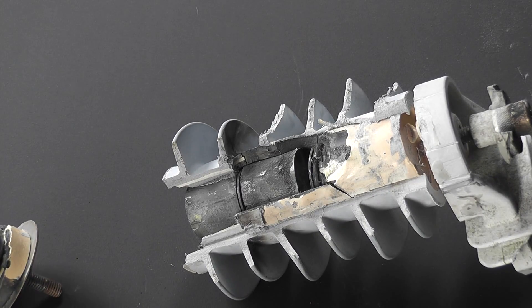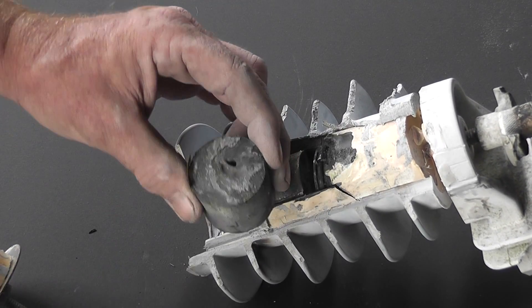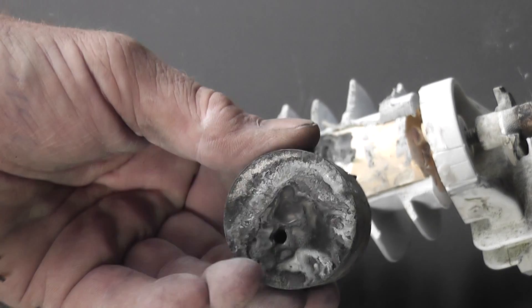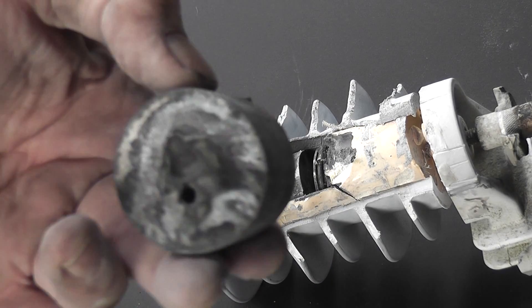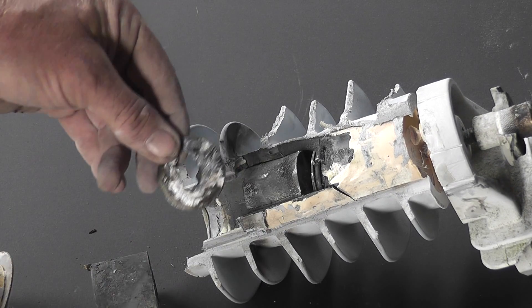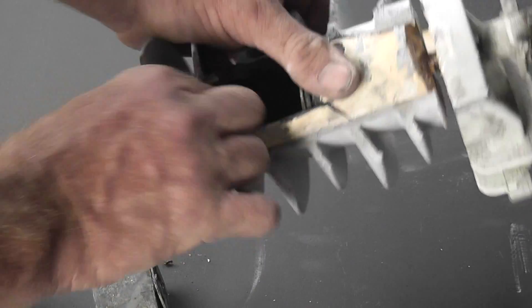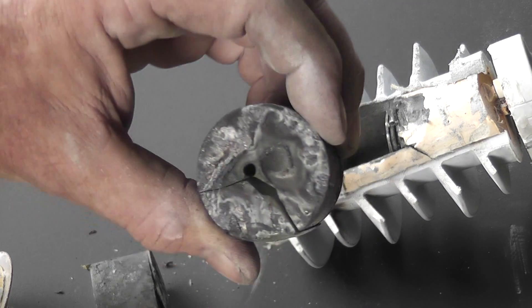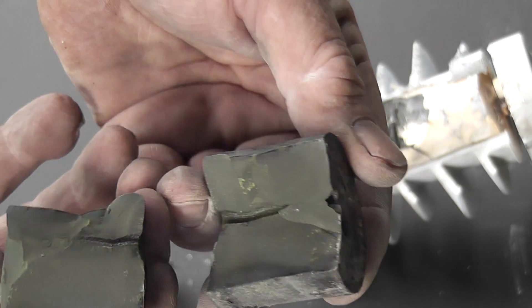Taking these out - they come out. These must be the clamping medium. They're non-magnetic. There's a hole burnt in there - I don't know if you can see it. I don't know if that hole is standard or not - it could be the arc gap or something. Then there's a steel plate, burnt a hole in it. Then the next one - that has cracked and split apart. It feels like a type of ferrite material.